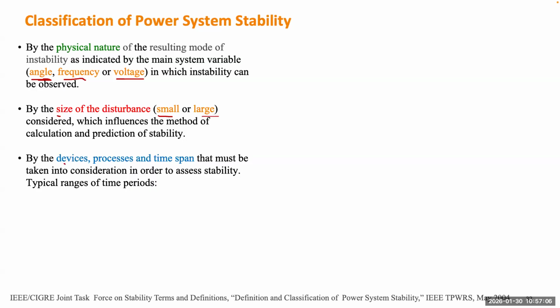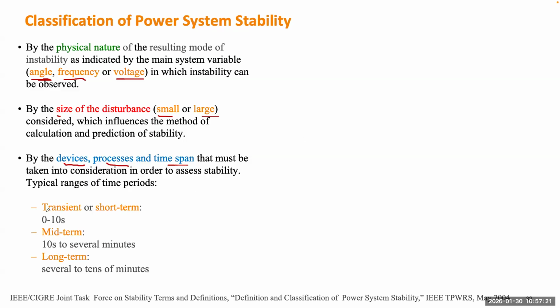There is also another idea, which depends on what the device is, what the process is, and also the time scale. If we consider those factors, we can categorize stability problems. Some stability problems mainly happen in the transient period, within 10 seconds, or maybe short term, a few seconds. Some happen from 10 seconds to several minutes, so we call it a midterm problem. And some stability problems need a long enough time, from tens of seconds to tens of minutes. So we call such a problem a long-term problem.